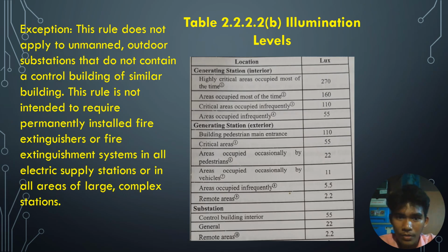Illumination level. For highly critical areas occupied most of the time, the limit is 270 lux. Areas occupied most of the time, the limit is 160. Critical areas occupied infrequently, the limit is 110. Areas occupied infrequently, 55. Generating station exterior. Building pedestrian main entrance, 110. Critical areas, 55. Areas occupied occasionally by pedestrians, 22. Areas occupied occasionally by vehicles, 11. Areas occupied infrequently, 5.5. Remote areas, 2.2. Substation. Control building interior 55, general 22, remote areas 2.2.